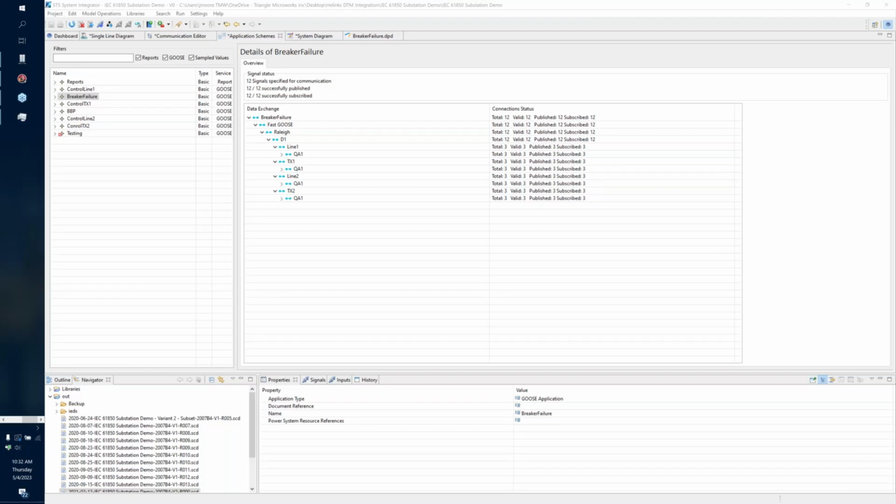All right, thank you, Christoph. As Christoph mentioned, the 61850 engineering process largely revolves around a class of tool known as a system configuration tool, or SCT. One such SCT, which Christoph has already introduced, is Helinks STS, which can be seen on my screen now. One of the purposes of a good SCT is to provide a layer of abstraction in the engineering process, allowing users to build and interact with their substation applications at a graphical level, and then letting the tool generate the necessary system configuration language, or SCL files, for us in the background.